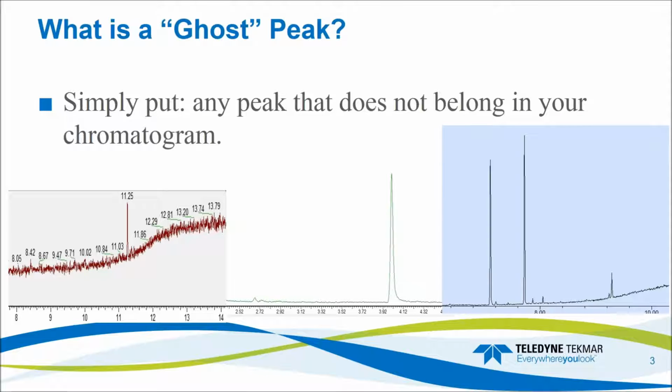All kidding aside, ghost peaks can be a really troublesome issue, especially if they start to interfere with your calibrations or if they start to affect your low-end sensitivity. So what is a ghost peak? Quite simply put, it's any peak that does not belong in your chromatogram.